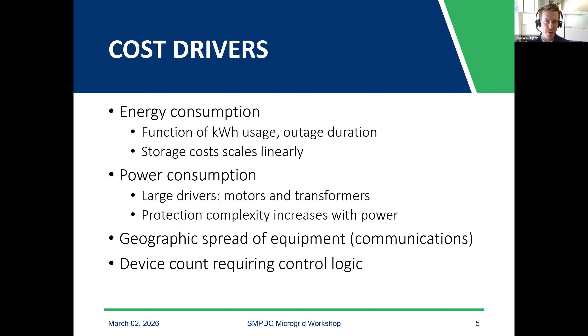The geographic spread of equipment matters too — if you have several facilities, that requires communication between all those devices, and each device probably isn't coming from the same vendor, so you have to integrate them. Another factor is the number of devices requiring control logic; as your application gets more specialized and unique, that requires more customized programming, which is a large cost driver you might not see if you're just looking at price trends for batteries in dollars per kilowatt hour.